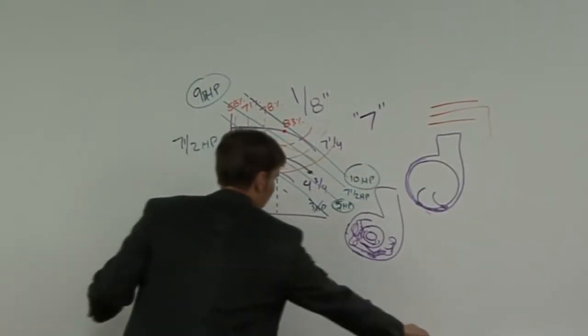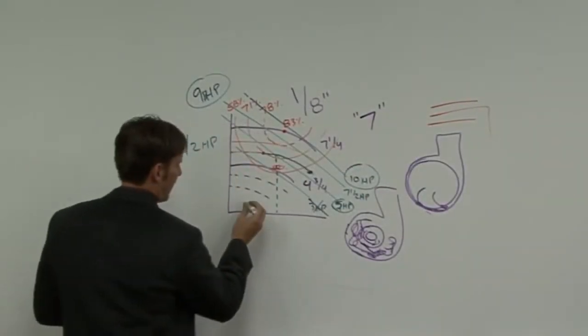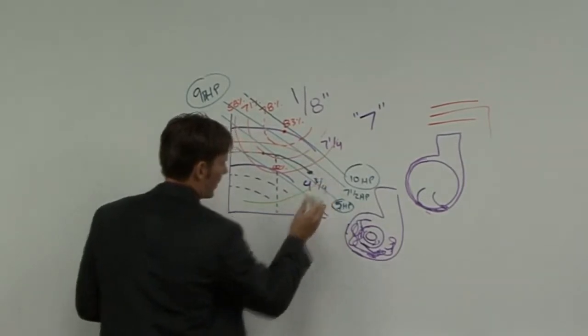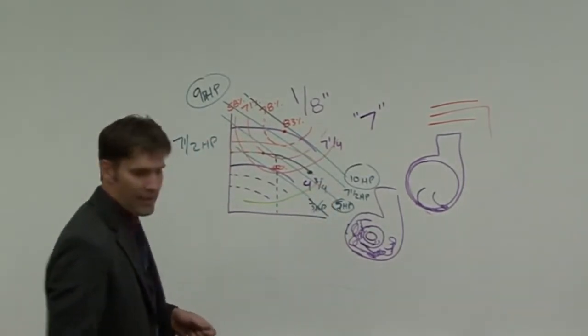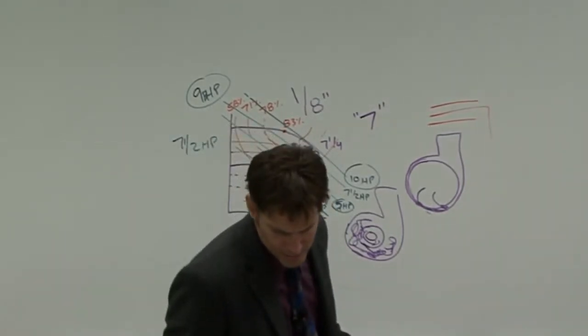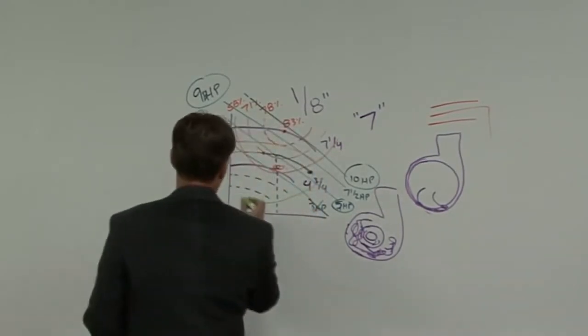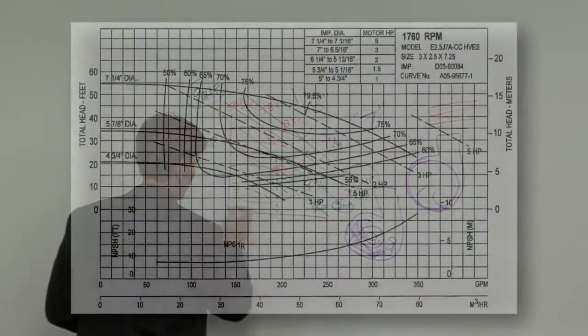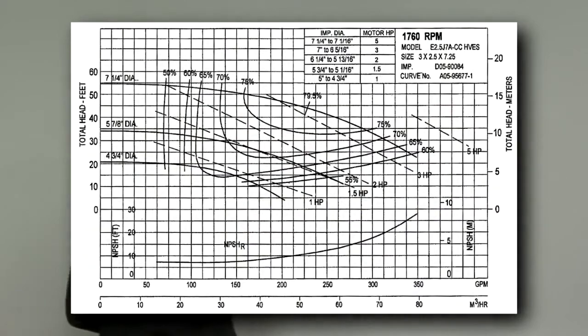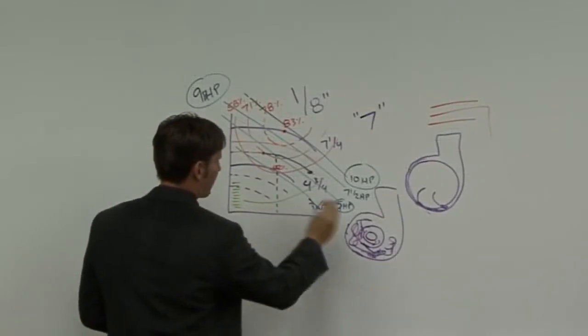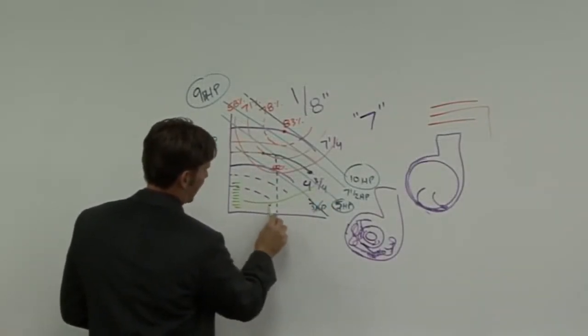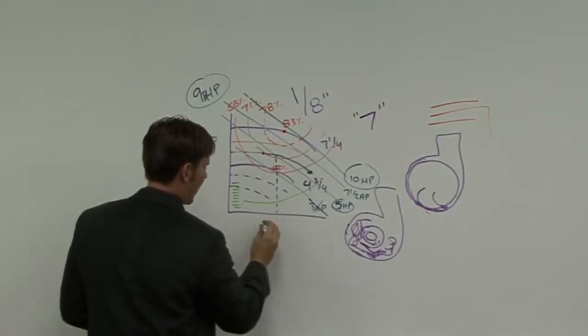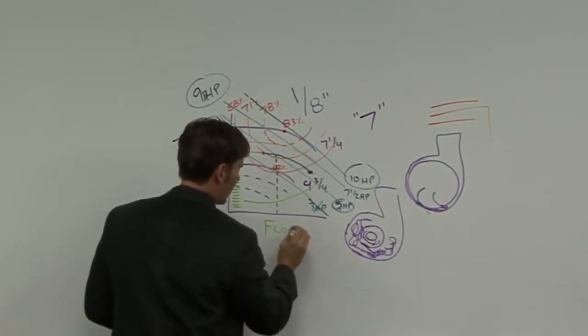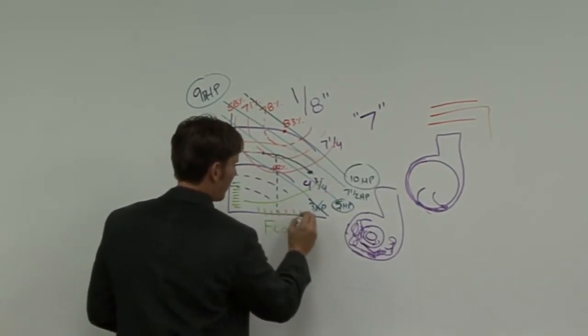Let's use a light green here. That NPSH-R is showing something like that. And then they've got the numbers listed over here. So as I have more and more water traveling through that pump, notice that my NPSH curve goes up as my flow across the bottom gets more and more and more.